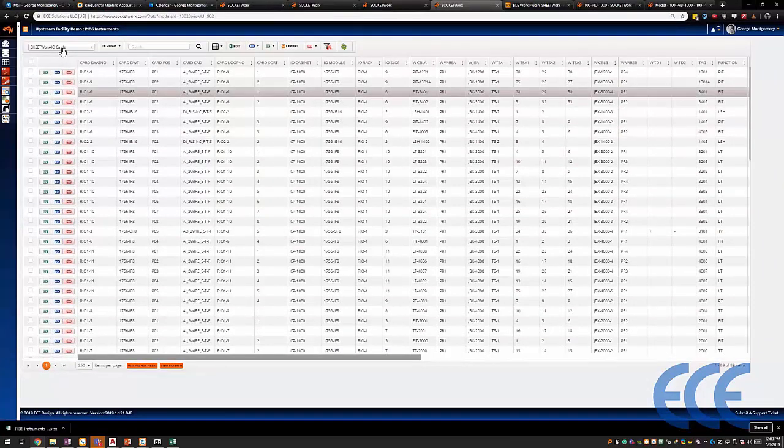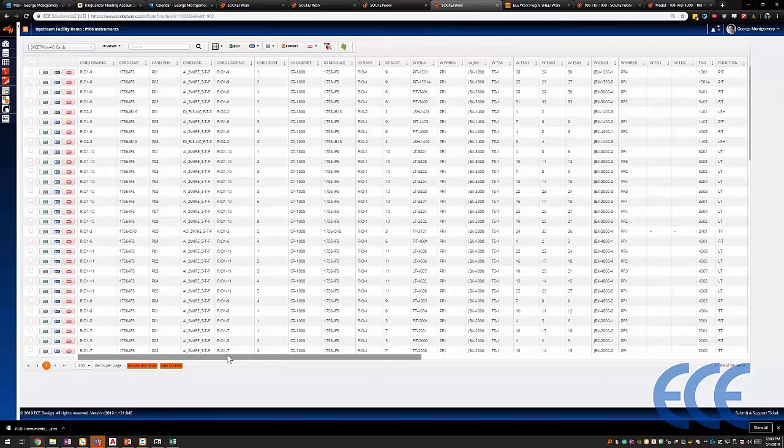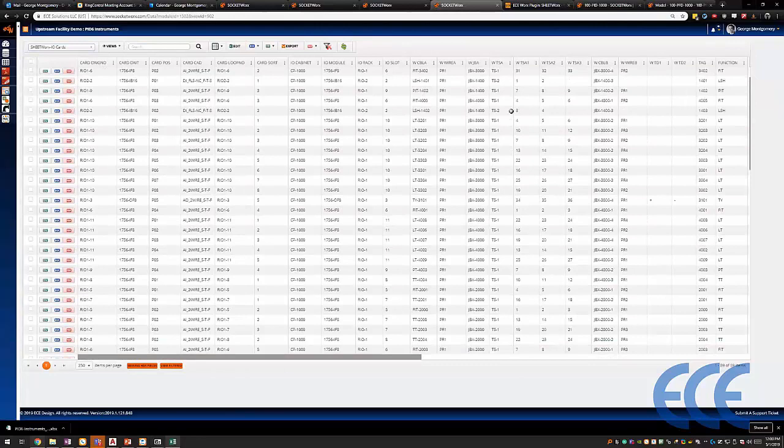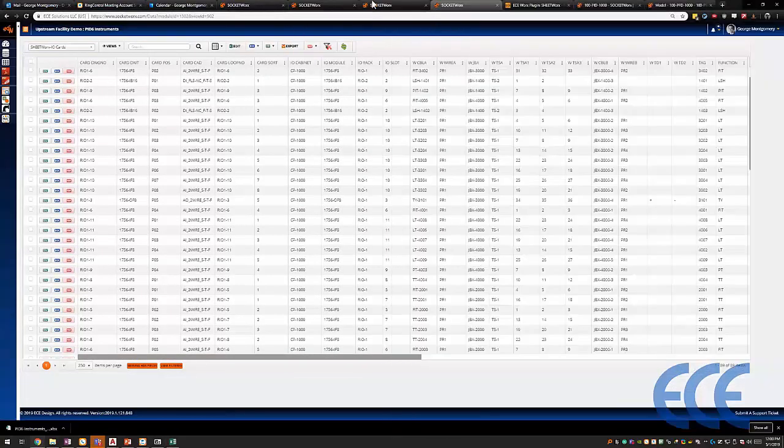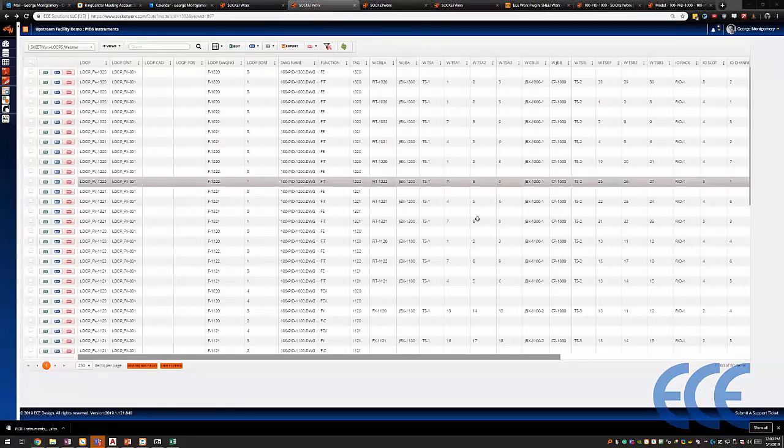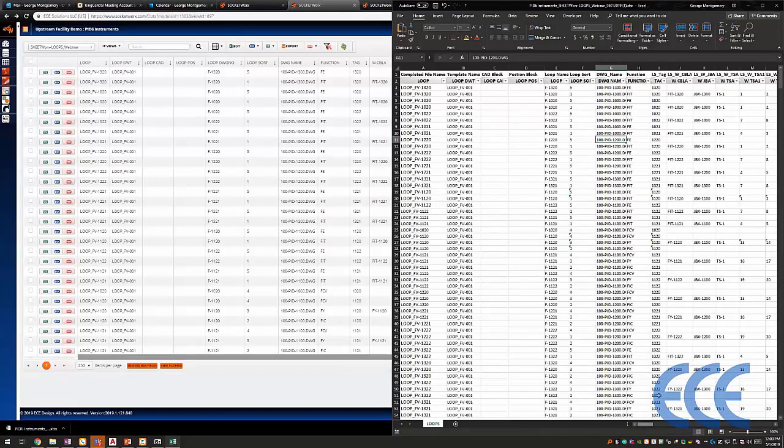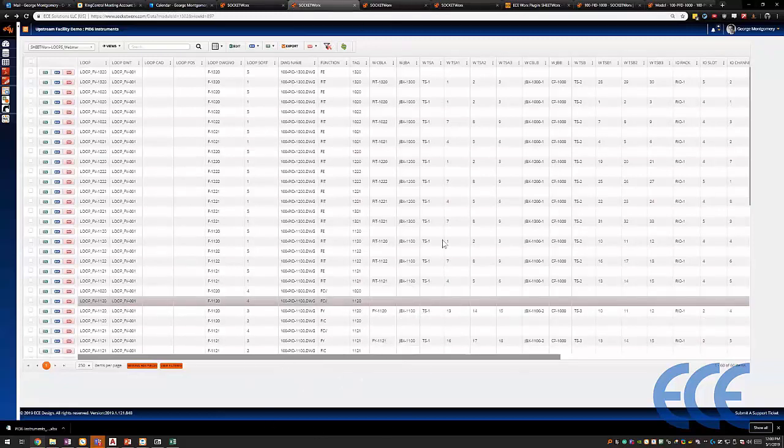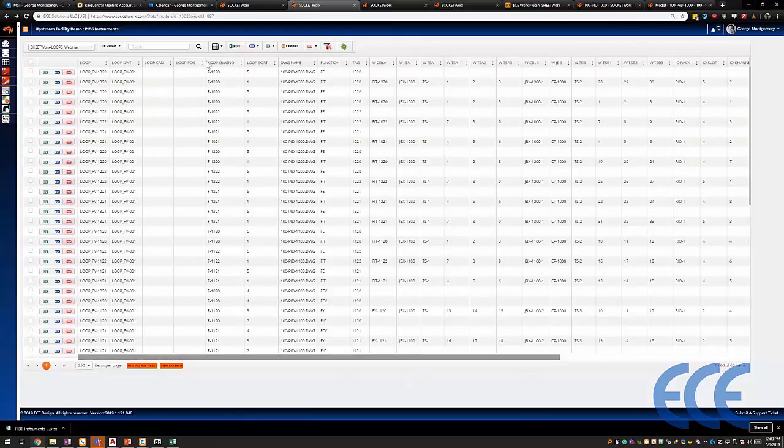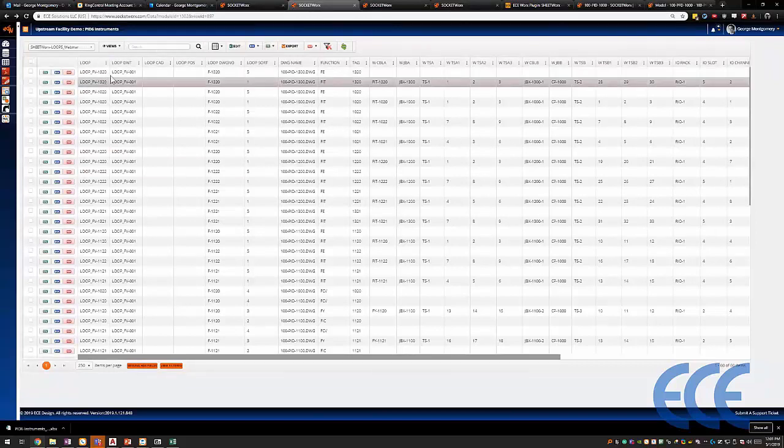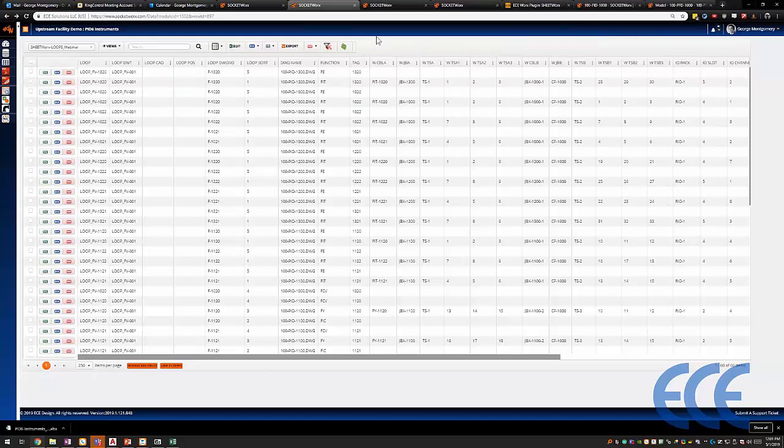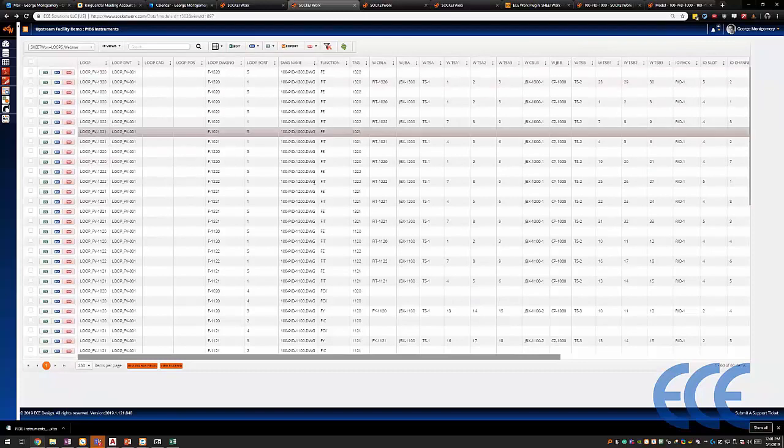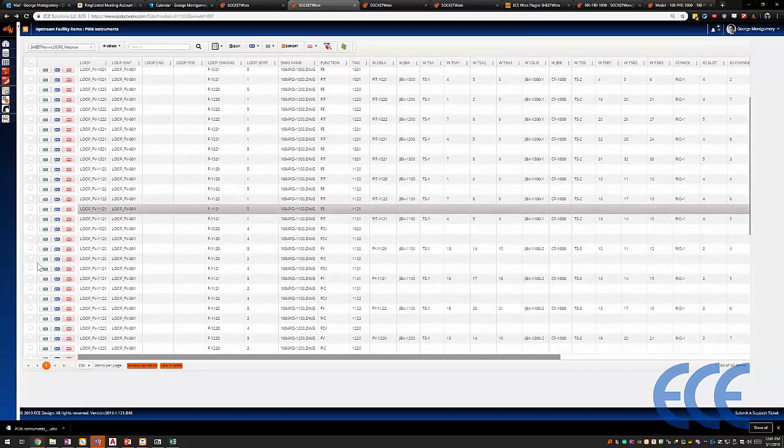So this I/O card sheet that you're looking at that's populated with all these different rows, this mimics exactly what I showed you here inside. Let me show you the loop one instead. Here's the loop worksheet. This loop worksheet mimics exactly what you're seeing here inside the Excel sheet. We've built this web interface really as a way to reach into existing databases and then pull data out of it, such as instrument bubbles on P&IDs. And then what we're doing is we're just populating additional data that we can use inside of Sheetworks itself. So everything that you're looking at here, all these data records, you can see the drawing name where it originally came from.